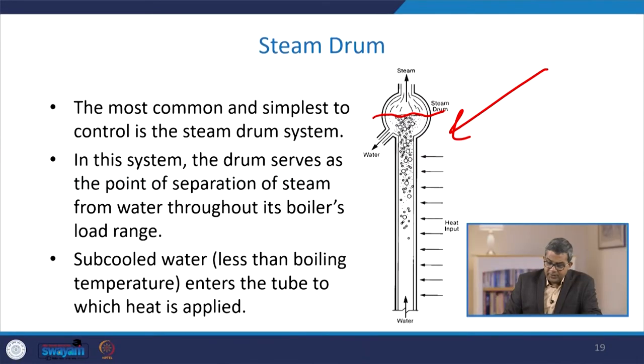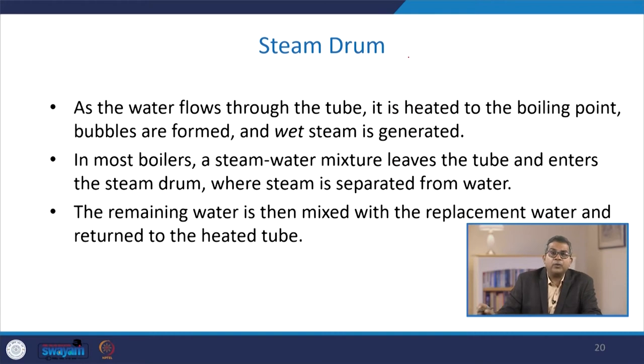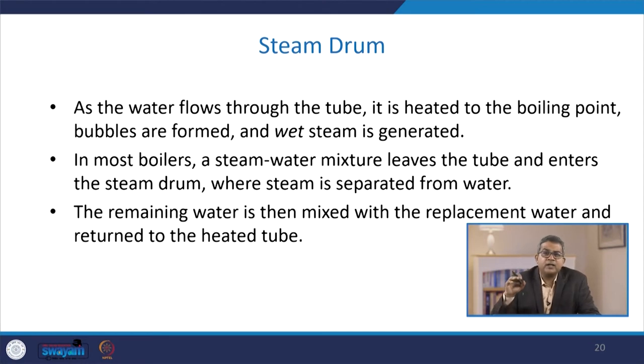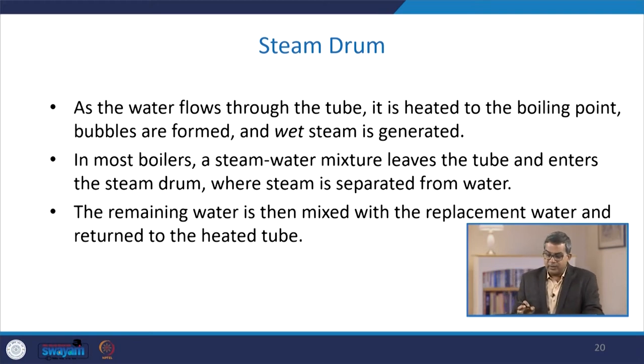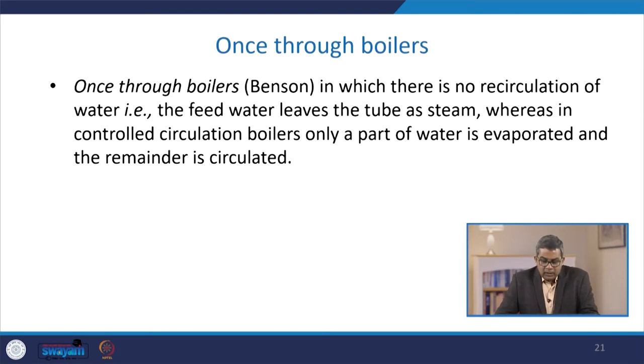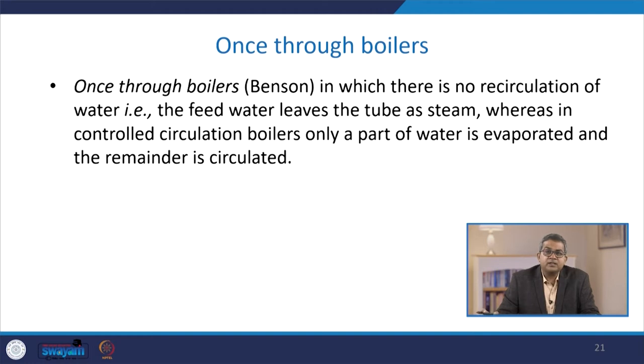Sub-cooled water at less than boiling temperature enters the tube to which heat is applied. As water flows through the tube, it is heated to the boiling point, bubbles are formed, and wet steam is generated. In most boilers, the steam-water mixture leaves the tube and enters the steam drum where steam is separated from water. The remaining water is then mixed with replacement water and returned to the heated tube. In once-through boilers such as the Benson boiler, there is no recirculation of water — the feed water leaves the tube as steam.